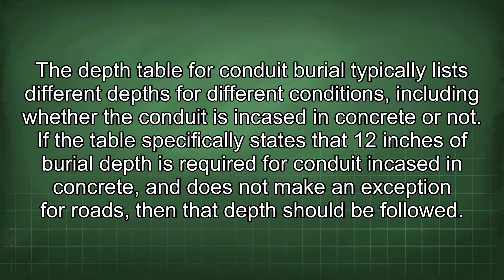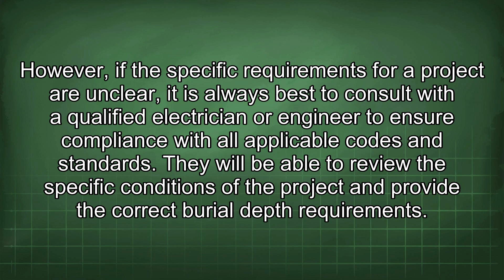The depth table for conduit burial typically lists different depths for different conditions, including whether the conduit is encased in concrete or not. If the table specifically states that 12 inches of burial depth is required for conduit encased in concrete, and does not make an exception for roads, then that depth should be followed. However, if the specific requirements for a project are unclear, it is always best to consult with a qualified electrician or engineer to ensure compliance with all applicable codes and standards. They will be able to review the specific conditions of the project and provide the correct burial depth requirements.